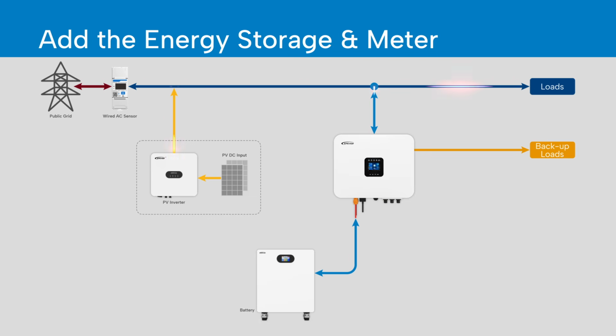Adding energy storage: a meter is installed between the grid and the PV inverter. The meter sends data to the hybrid inverter through a controller. The energy storage system keeps the meter reading near zero. When excess solar power is detected, the battery charges. When there is a power shortage, especially at night, the battery discharges to support the load.